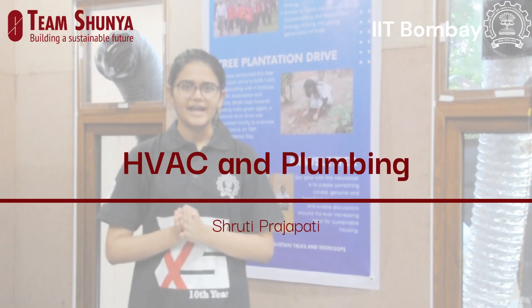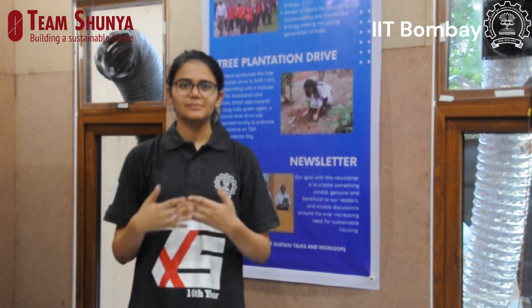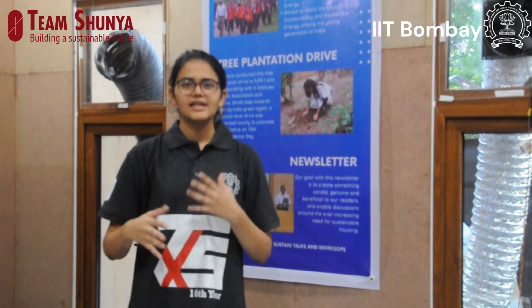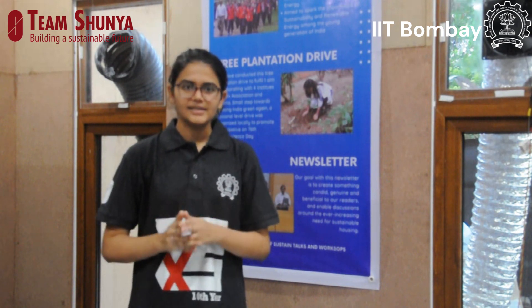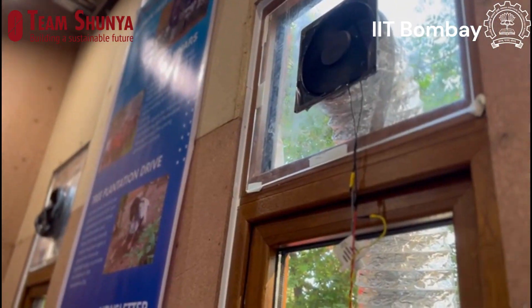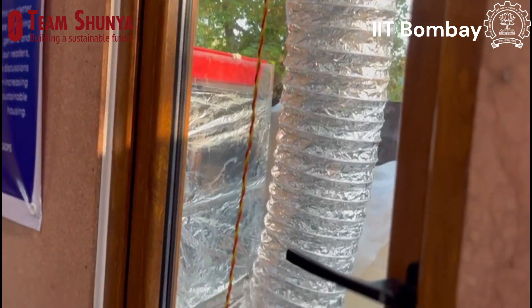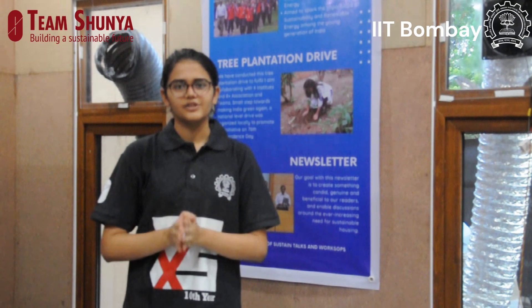The energy-efficient HVAC in the house is designed along with thermal storage of chilled water, which ensures cooling and comfort conditions even during blackouts and off-solar hours. The chilled water is supplied into fan coil units that maintain the temperature of the room. For humidity control, we have a liquid desiccant-based unit placed just outside the house with a duct extending into the house. The exhaust fan absorbs moist air from the room, processes it, and returns it through the return line, maintaining optimal humidity levels.